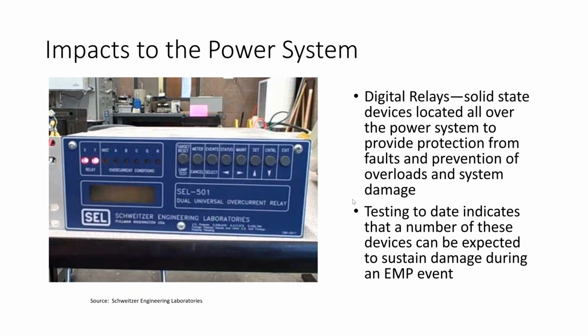Now, you can't see the whole relay here, but I can tell you it's encased in a metal case. That metal case is probably installed in a rack inside the substation's control room. That control room may either be built out of sheet metal or have metal shielding on it. All of these factors would enter into trying to reduce the radiative energy, I'll say, that the relay would face. So those kinds of radiative impacts tend to be less of an issue for the digital relays. The bigger threat is probably the conductive energy. Now, I mentioned that there's a copper control wire that takes the signal from the sensor and brings it into this device.